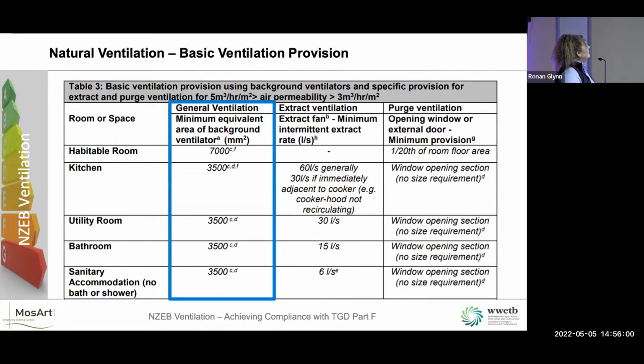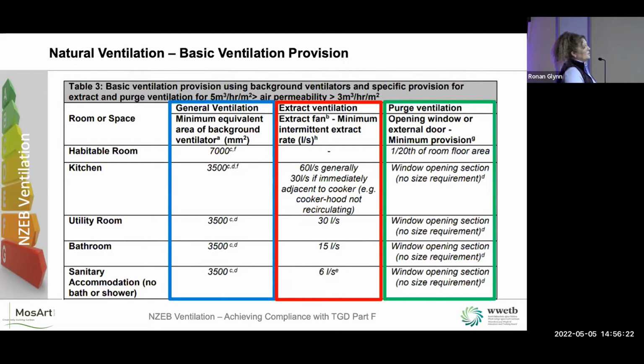The extract then is given by the table in part F. So you must have these kind of extracts from the different rooms depending on the function of the room and the requirement. So they also need to be checked, and the validator comes out and checks the actual flow rates for natural ventilation. There was a question there about purge ventilation. So I have a slide on that further on as well. So purge ventilation is a requirement. I had somebody the other day tell me that you don't need openable windows anymore if you have an MVHR. So God love him, if his electricity ever fails, he's no way of opening a window. So it is a provision and it is a requirement.